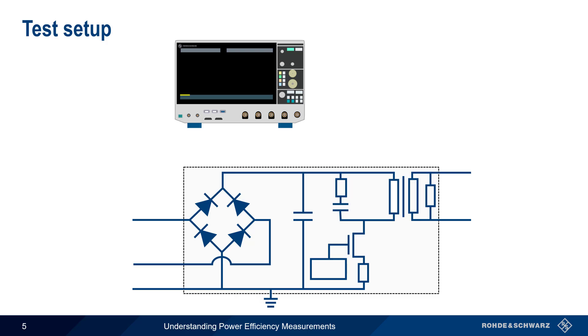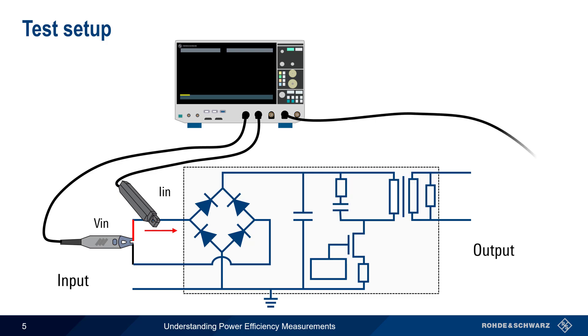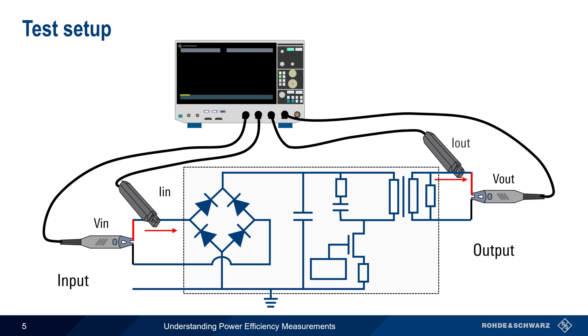Let's take a graphical look at power efficiency measurements. On the input side, a voltage probe – often a differential probe – is used to measure input voltage, and a current probe also measures the input current. Similarly, on the output side, a second pair of voltage and current probes is used to measure the voltage and current at the output. As can be seen in this illustration, power efficiency measurements therefore require a total of four oscilloscope channels.